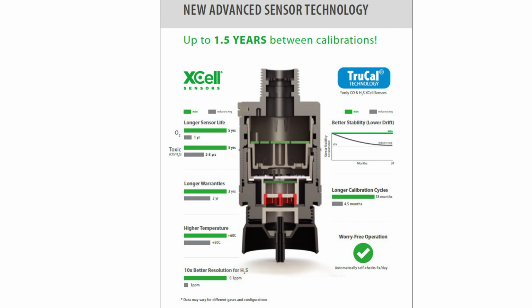Another question is, how often should the sensors be calibrated? The simple answer is there is no simple answer. It all depends on what kind of environment your sensors are located in and your facility's individual safety plan. While the Ultima Xs that are being phased out tended to be calibrated around every 3 months, the new Ultima X5000s with XCell sensors and TruCal technologies can last anywhere from 12 to 18 months between calibrations, a considerable manpower and cost savings. However, again, this all depends on each individual facility.